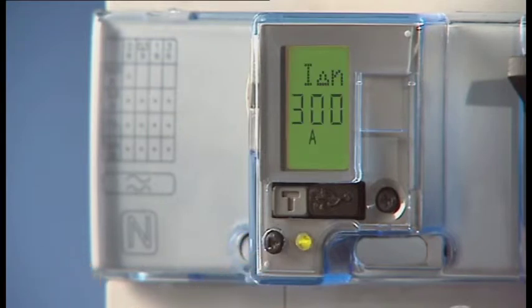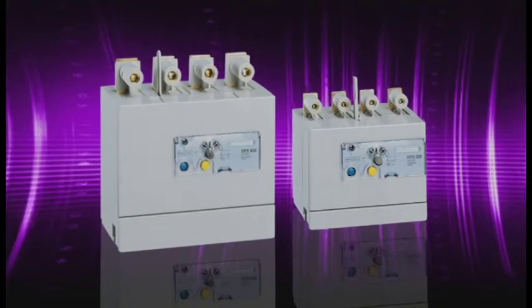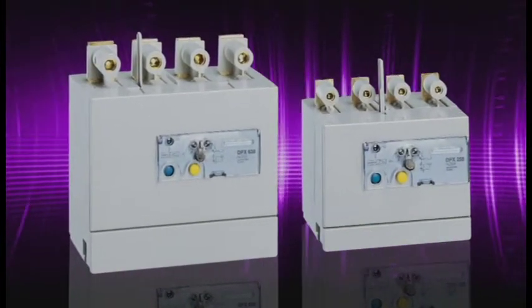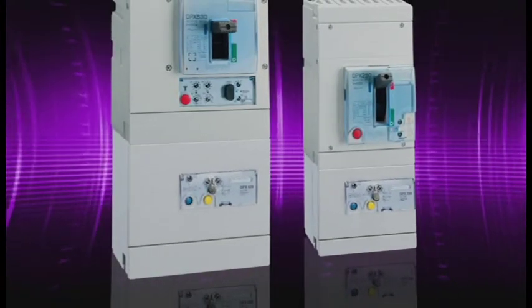The DPX Cubed MCCBs with integrated earth leakage protection allow the setting of current values and time delay for tripping. The DPX 250 and DPX 630 ranges need to be equipped with a corresponding earth leakage module in order to ensure protection against residual currents.